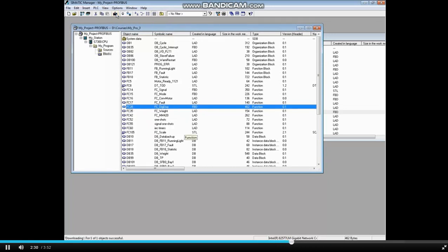The problem is that after creating Function 28, we made the call to it but forgot to download it. Then when OB-1 was downloaded, it went looking for the subroutine and couldn't find it.